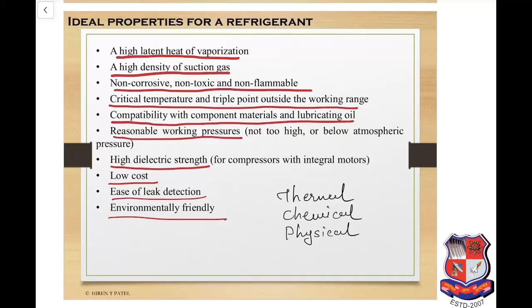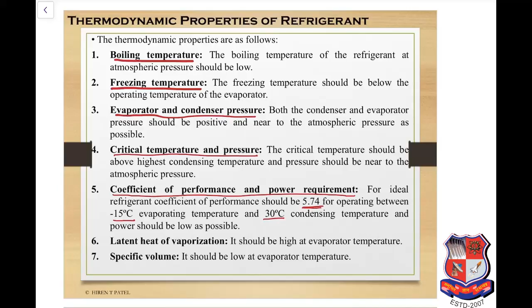First one is the boiling temperature, which should be low. Then the freezing temperature should also be low. For evaporator and condenser pressure, both should be positive and near to the atmospheric pressure if possible. Then critical temperature and pressure: the critical temperature should be above the highest condensing temperature and the pressure should be near to the atmospheric pressure. Coefficient of performance and power requirement: for an ideal refrigerant, the coefficient of performance should be 5.74 for operating between minus 15 degrees Celsius and 30 degrees Celsius temperature range. Latent heat of vaporization should be high at evaporator temperature and specific volume should be low at evaporator temperature.